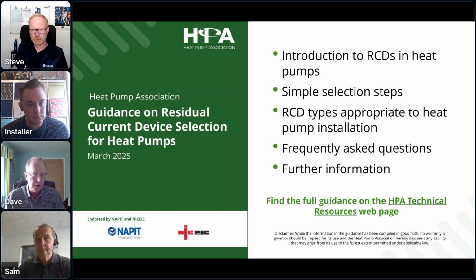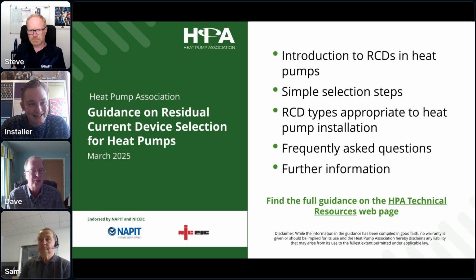And from the heat pump point of view, if we are going to achieve the targets that we need to in terms of deployment of heat pumps, consumers have to know that they're safe, as you would expect with any electrical appliance, but also they have to know that they can rely on their heating system. So there are two things that can go wrong if you make the selection incorrectly. One is that it fails to trip when it should, which is then that risk to safety, personal safety. But the other side of the coin is tripping when they shouldn't, and then your heating system goes off when it shouldn't have gone off. So I think I'll hand over to technical colleagues to explain what causes those things, but that's why selecting the right RCD is really critical.